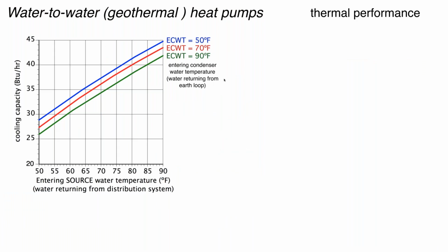Water to water performance, it's the same concept as what we looked at for the cooling performance of air to water heat pumps. As the entering condenser water temperature, this would be the water coming back from the earth loop that is picking up heat at the heat pump and taking it back out to dissipate into the ground, you can see as that earth loop warms up over the course of the summer, or if the earth loop was undersized, we're starting to lose cooling capacity.